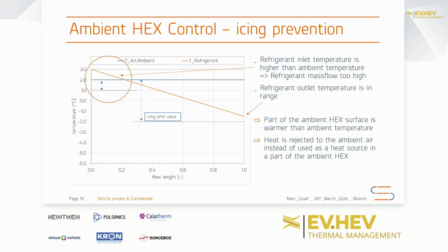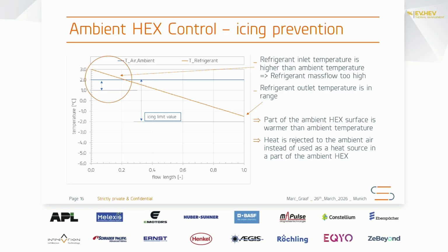If you look, for example, at the ambient air as a heat source, like I said before, we are controlling this in a way that we can operate continuously so that the ambient heat exchanger does not ice up. And in the end, if we have a sufficiently high airflow through the heat exchanger and a low temperature difference, those are the main influence factors there, we are able to operate this continuously. This is all based on a patent that is publicly known, so it's published, so you can look into that, or I can name you the number if you have interest in that.